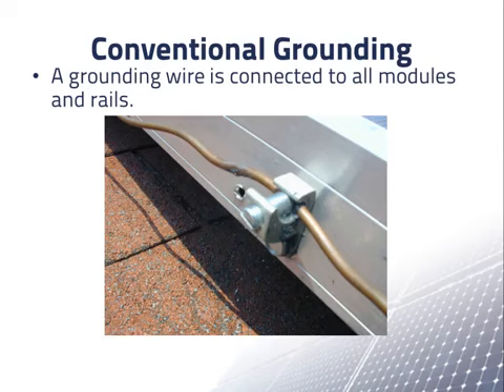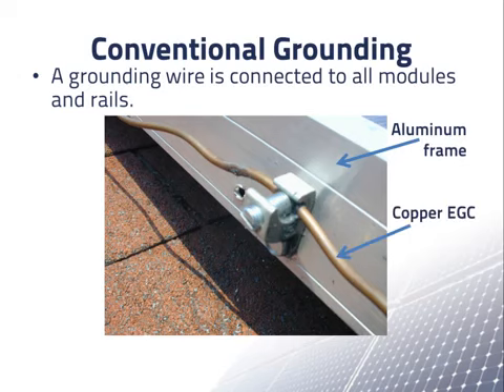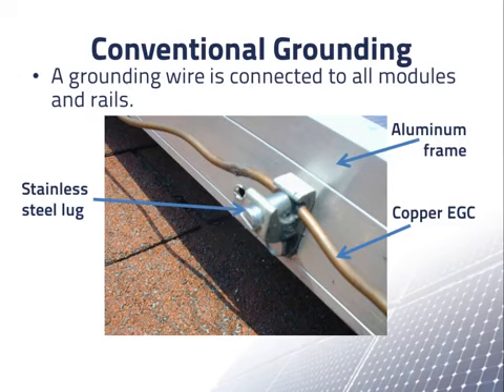We see the aluminum frame of a PV module here, and the copper equipment grounding conductor here. To connect the two, we have a stainless steel lug. You can't see it, but the lug has ridges on the bottom, so that it digs into the aluminum and penetrates the non-conducting surface. The copper wire is positioned so that it is never in direct contact with the aluminum.